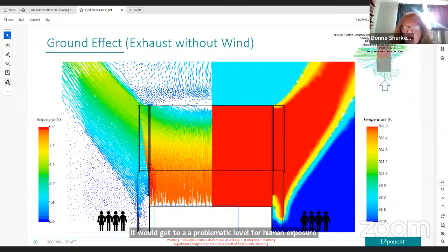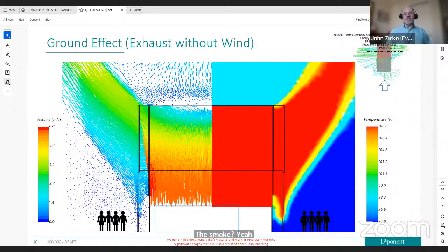Thank you. So, Mr. Zico, if there were a fire within the underground substation, can you tell me where that smoke would be vented? In the event of a fire, each area of the station, so each transformer vault, reactor vault, switchgear room, control room, etc., has its own intake and exhaust fan that take the supply and discharge into a common duct system that terminates in this intake and exhaust shaft. If there were a fire, the fire alarm system is wired to shut the fans off for the particular zone where the smoke is detected, as well as close the dampers. The fire would then be dealt with either with extinguishers locally or through the fire suppression systems that we've installed. And then on top of this ventilation system, there's a smoke evacuation system that's manually activated, and that would be done under the direction of the Cambridge Fire Department.